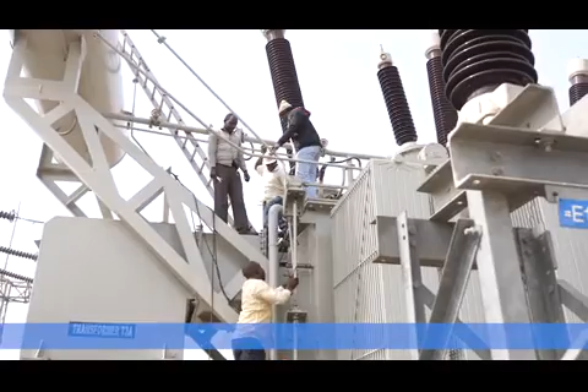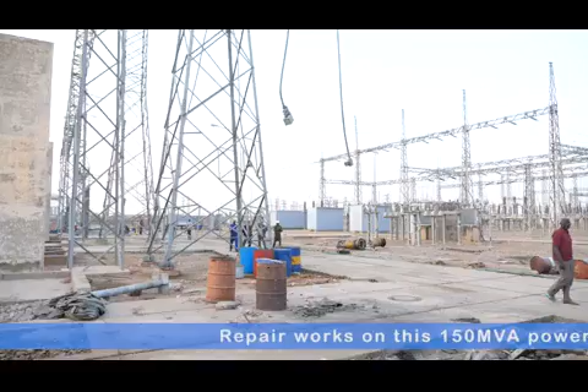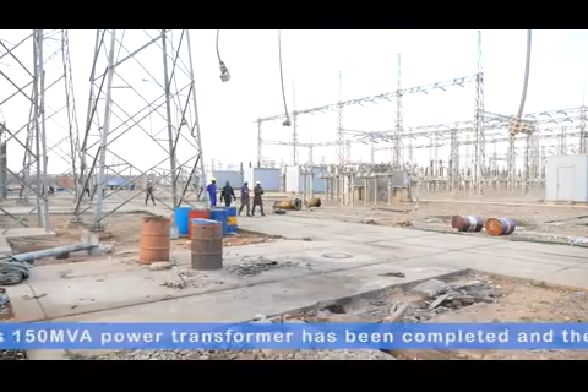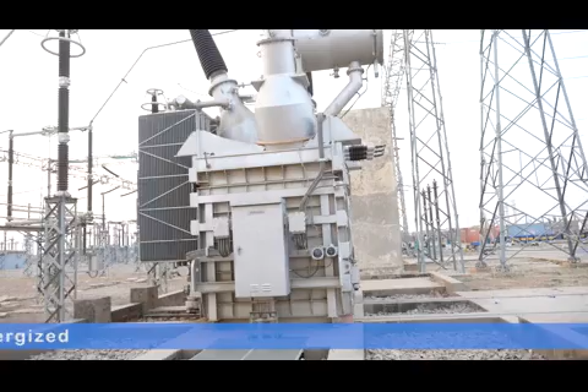During this repair, how does TCN ensure bulk power delivery to Kano Disco? When we had the problem with T3A — we used to have three transformers of 150 each, that is 450 MVA capacity. With the T3A problem, we only have 300 MVA now. So what we did was share the load between the two remaining transformers, since they were not carrying maximum load.